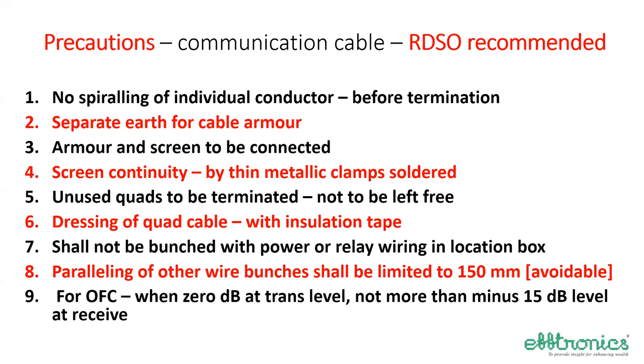And a separate earth for cable armor. If a screened cable is used, armor and screen both are to be connected. Screen continuity is very important. Screen may be available, but unless you connect that screen to the earth, it is of no use. So by a very thin metallic clamp, it shall be soldered, not just tied. Unused quads are to be terminated, not left free, because they may get earthed and carry charge and other problems will be there. And they may touch the terminals where signal carrying conductors are already terminated.